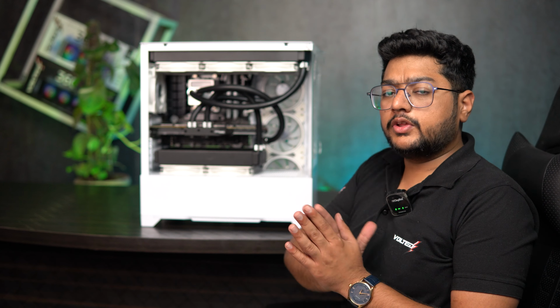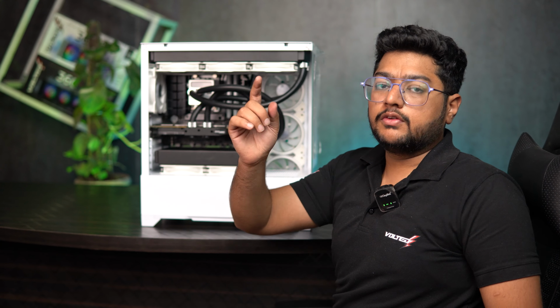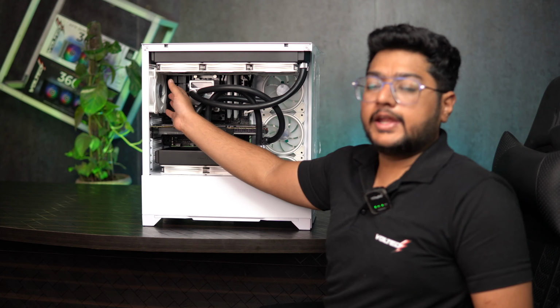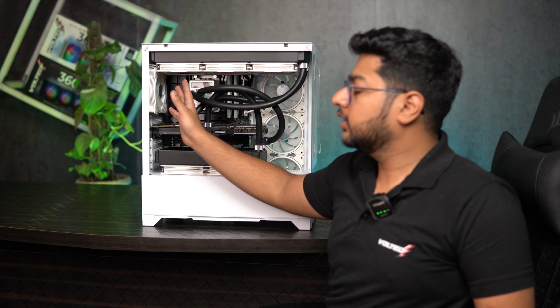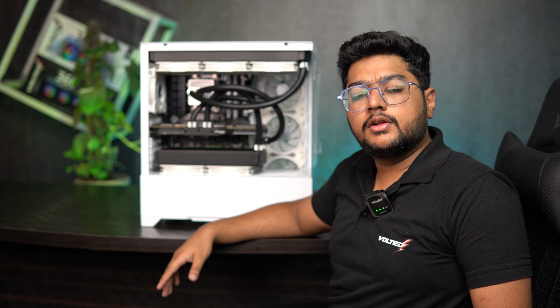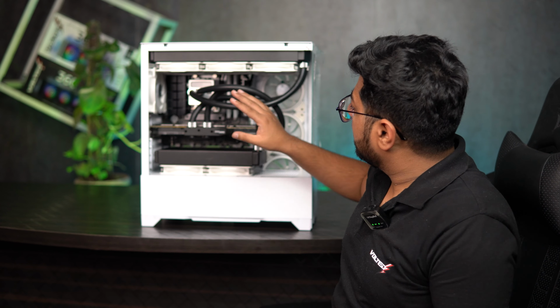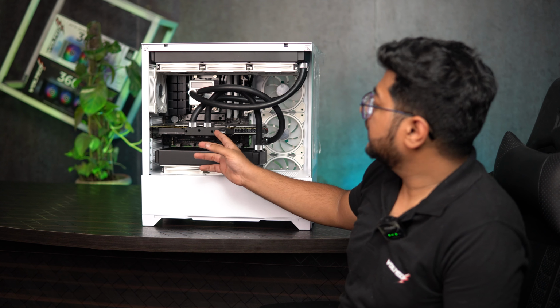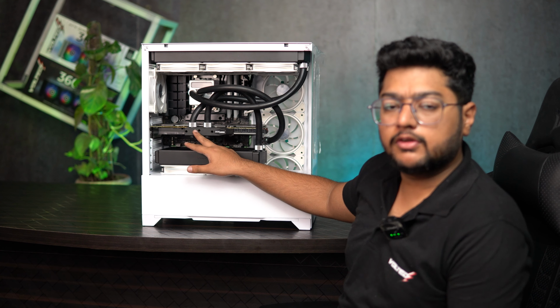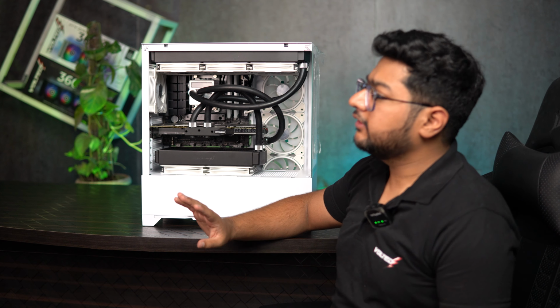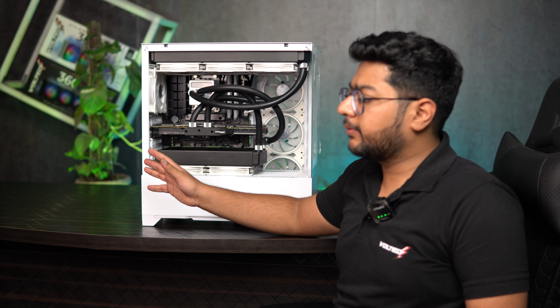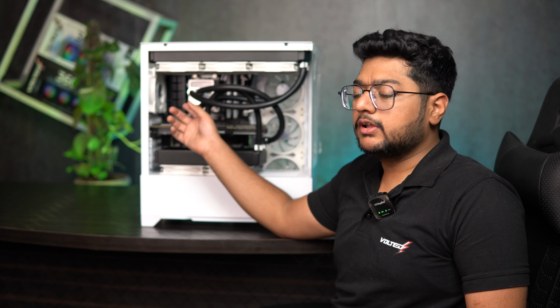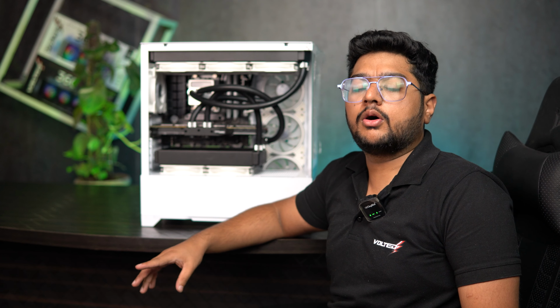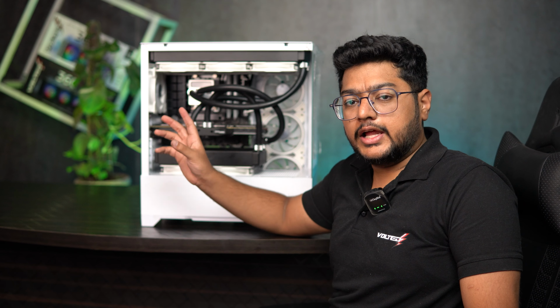Now that all the bends are done, we'll first do a pressure test. We'll connect our pressure kit to one end of the loop and apply some pressure, so that if there's any chance of a leak, it happens right away and not after we fill in the liquid. We'll leave the pressure applied for approximately 30 to 45 minutes and monitor the needle, which should not drop from its pressure point during that time.